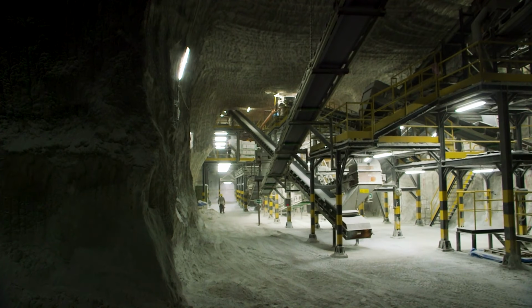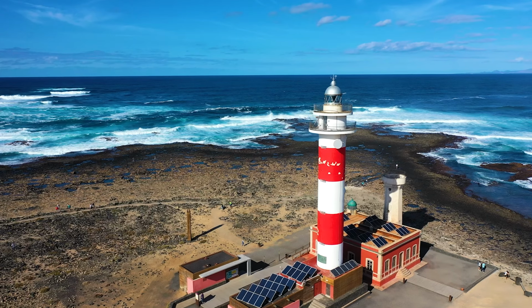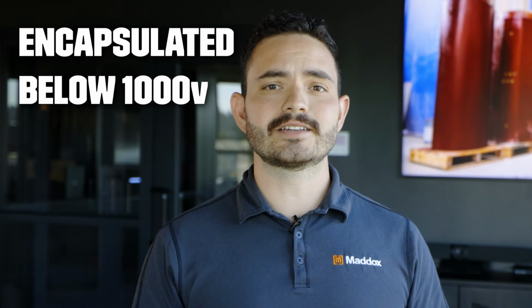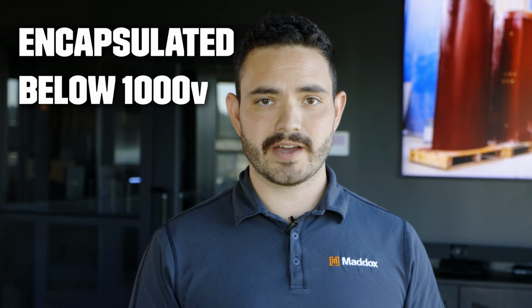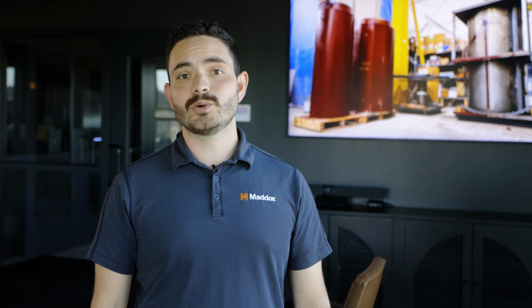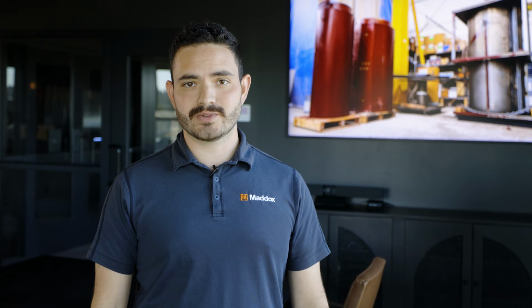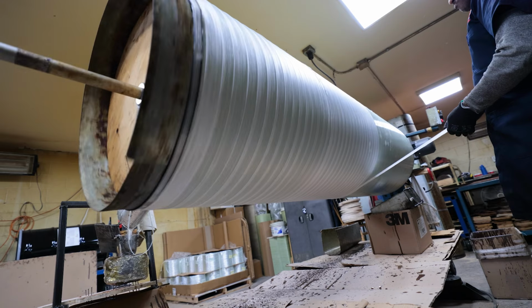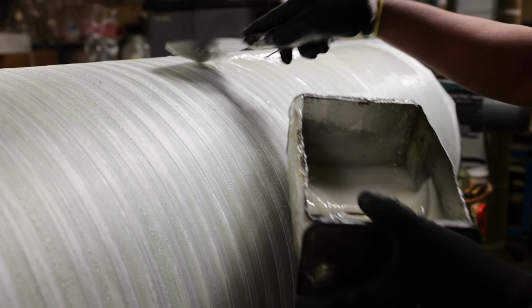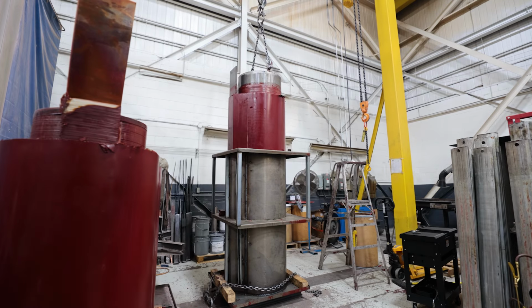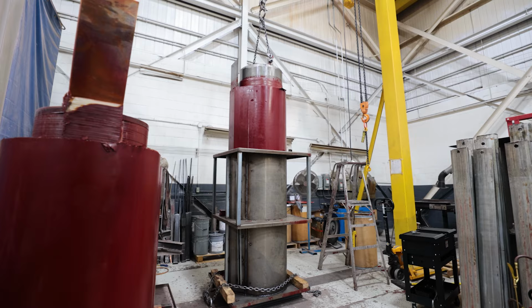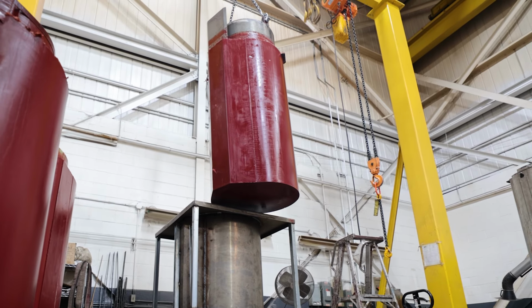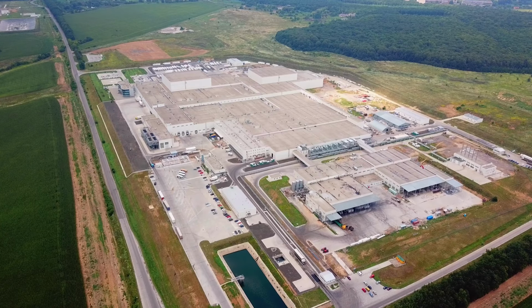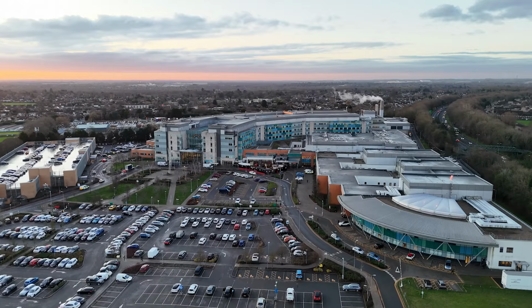You'll see them in mines, pulp and paper facilities, marine environments, anywhere durability matters in lower voltage applications. Encapsulated transformers are ideal for applications below 1,000 volts. Above that voltage range, you'll need a cast coil transformer. Cast coil units are dry type transformers with a cast resin mold just around the windings. The windings are first wrapped in fiberglass and then placed into a mold. Resin is then poured or vacuum cast over them and then cured to form a solid structure. You'll typically find these units in industrial plants, medical facilities, and data centers.